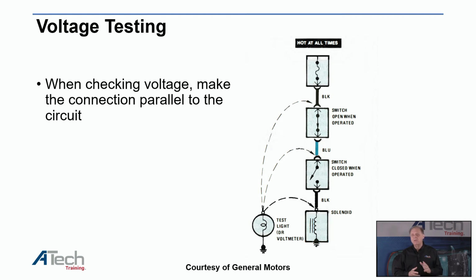Again, I'm only moving my red lead three times: to my battery, to check I have a good ground, before my load, and after my load. That's the way you should do it. If I have two loads, I check before and after each load, or individually if you want to do that. But that's a good way of breaking the circuit down.